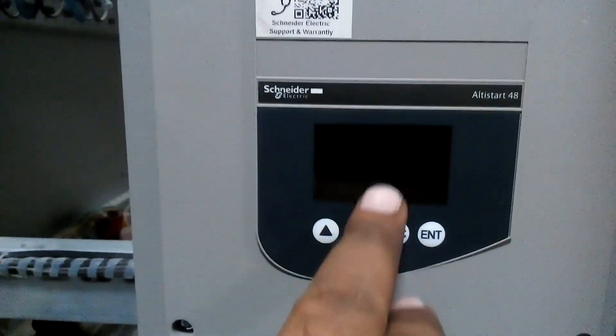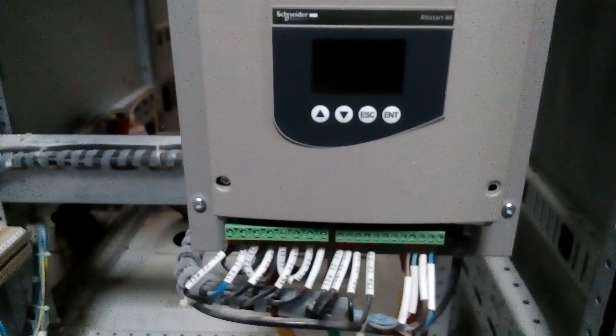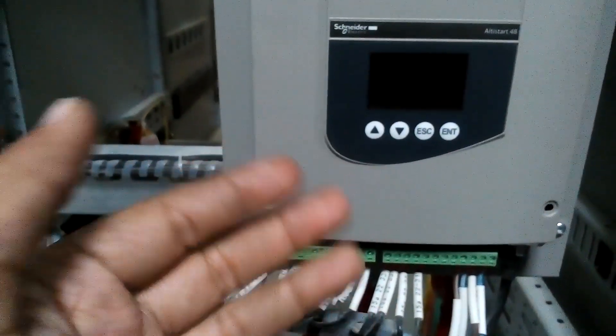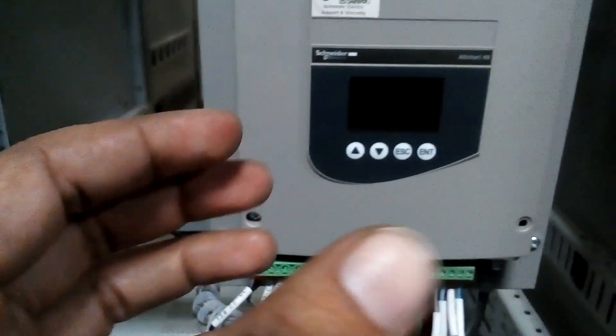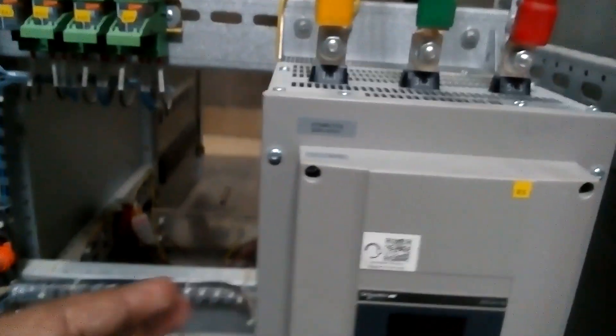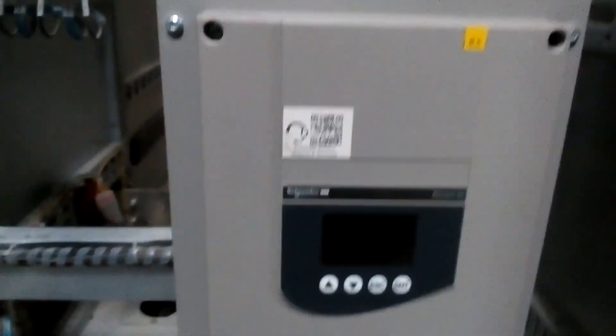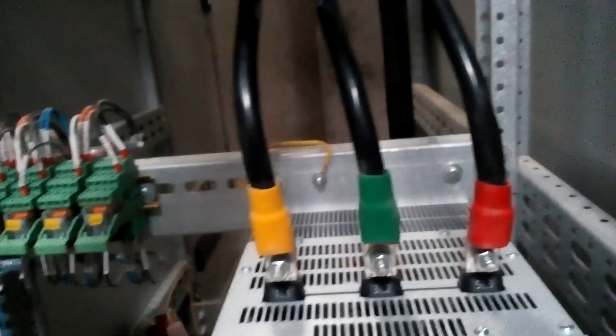Here you can see the soft starter — Schneider Altistart 48 installed here. This starter's function is to give a soft start to the motor initially, because the motor starting torque is high. We start the motor at slow speed; when it reaches running speed and runs normally, the soft starter gives a signal through a relay, that relay operates the bypass contactor, and the bypass contactor then energizes, supplying power to the motor.